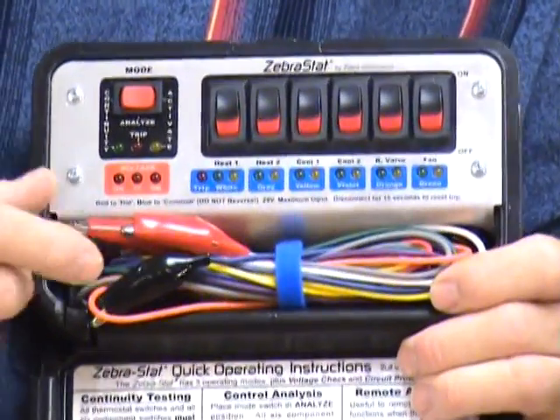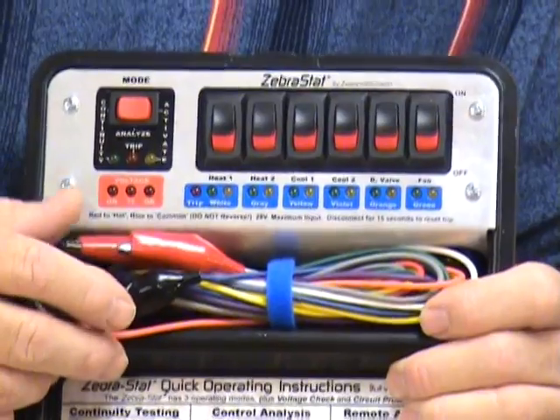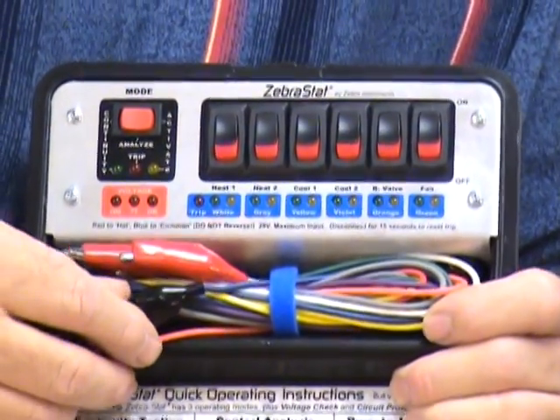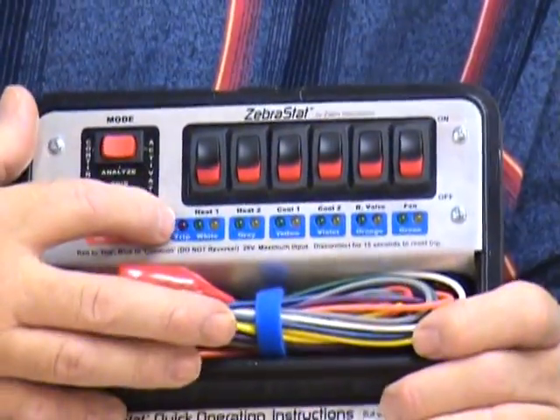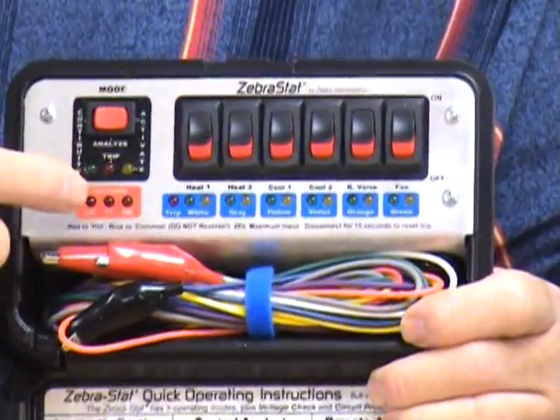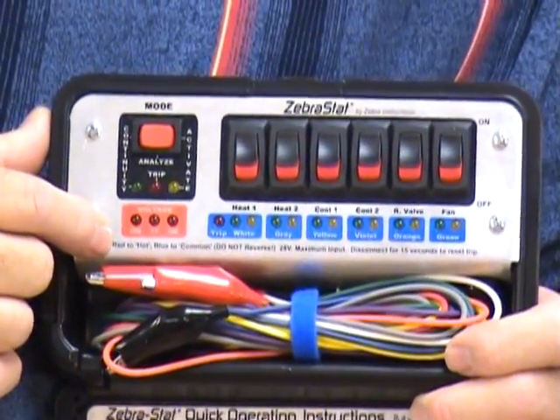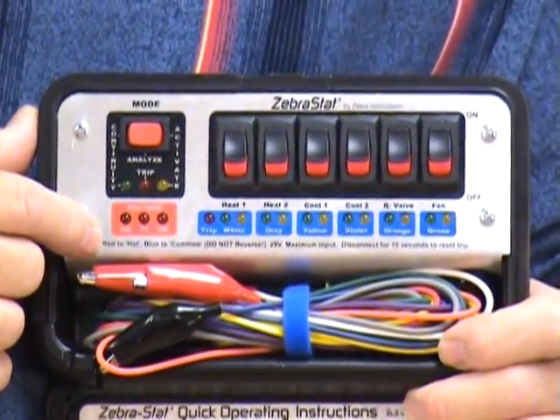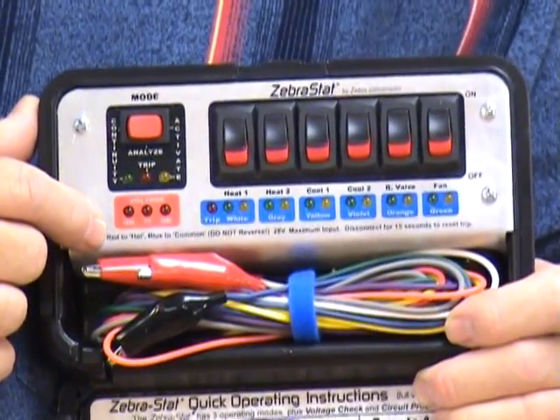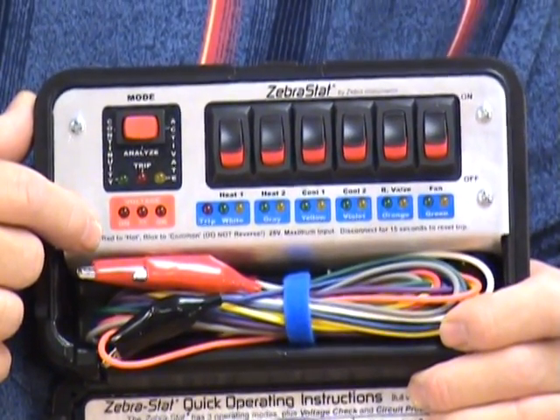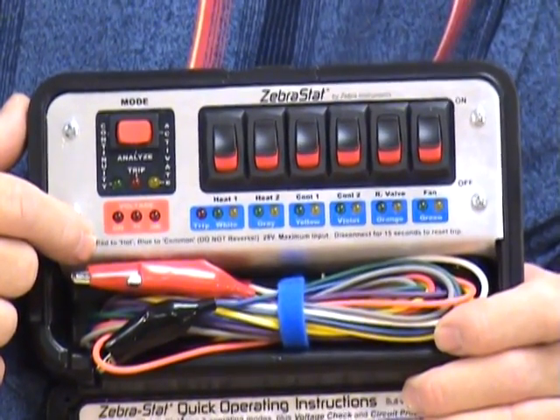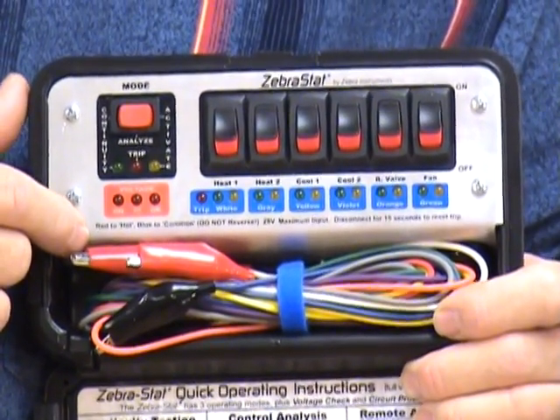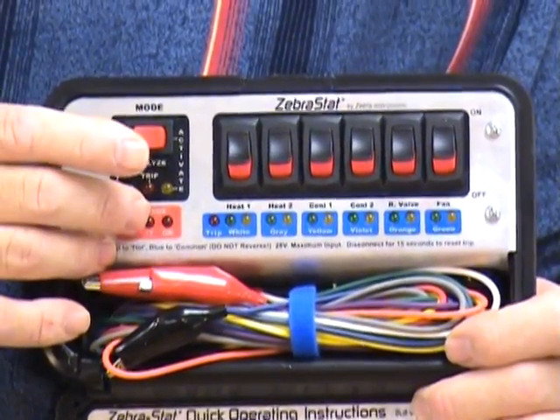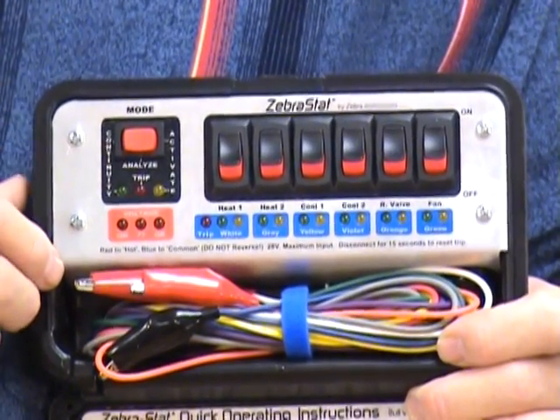The fifth feature is that you can use the ZebraStat as an automatic resetting circuit breaker. And that's what this light and this light come into effect. It acts as a 3 amp or a 5 amp circuit breaker, so you can test circuits without fear that you're going to wreck a circuit board. You might have to take a fuse out looking for a short, for instance. And when you use this according to the directions, it will keep you from damaging those boards.